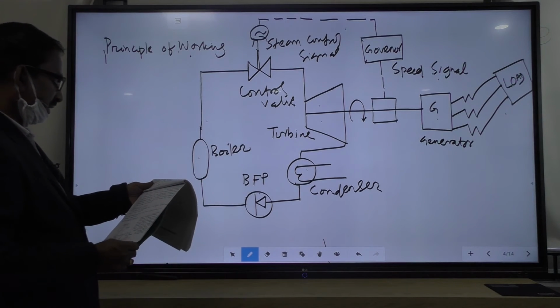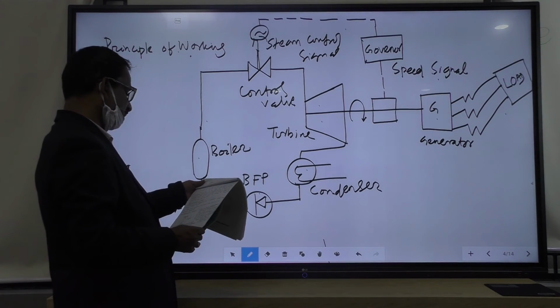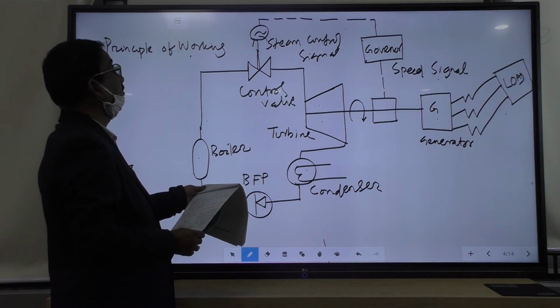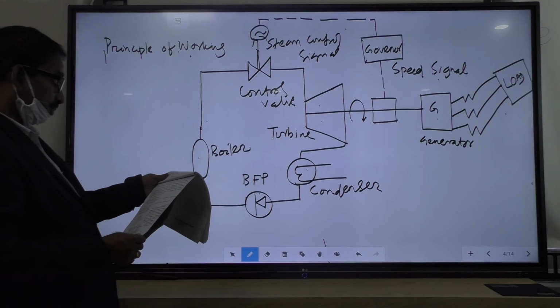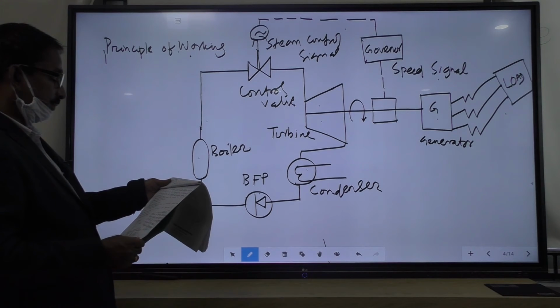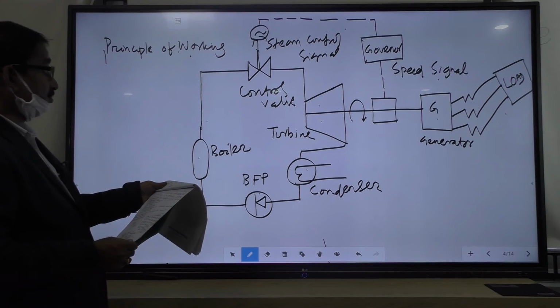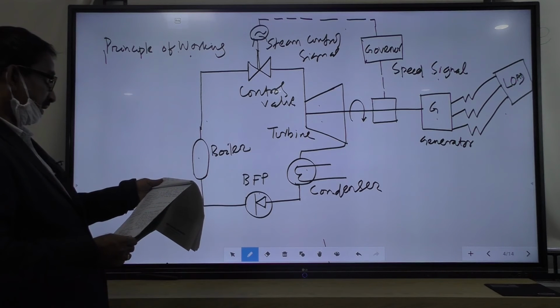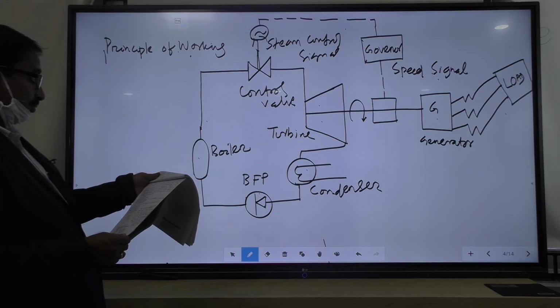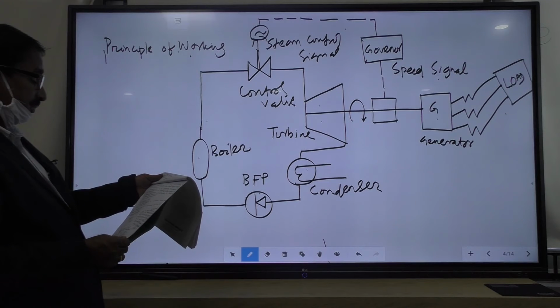The speed change caused by load change is sensed by a device called a speed sensing device. Corresponding to the difference between the design speed and the actual speed, a signal is generated which actuates the control valve to establish steam flow to the machine.